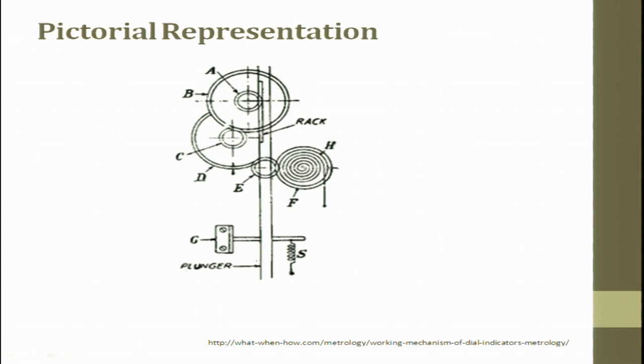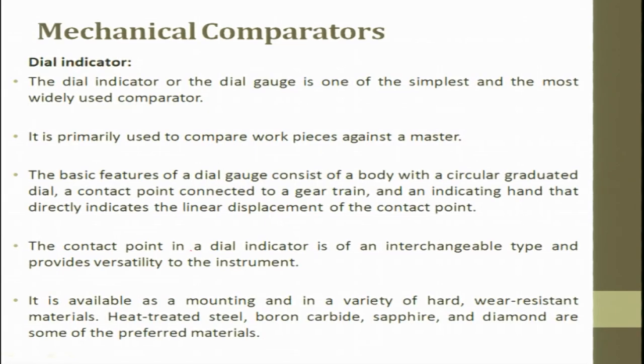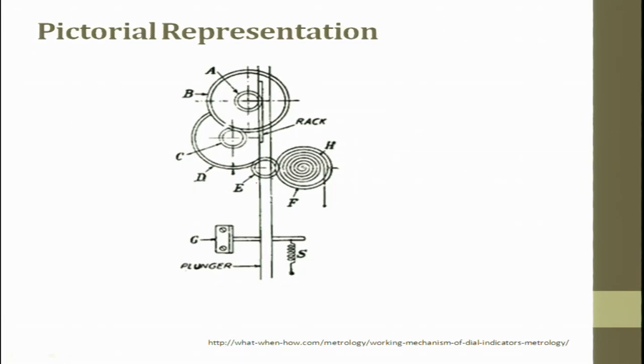The plunger moves; there is a spring loading and the displacement will move the coil spring — you have a rack. From the rack you have a pointer which is displayed on a dial gauge. The contact point in a dial indicator is of an interchangeable type and provides versatility to the measurement. The contact point which touches the workpiece is available in a variety of hard wear-resistant materials: heat treated steel, boron carbide, sapphire, and diamond are also used at the contact tip.